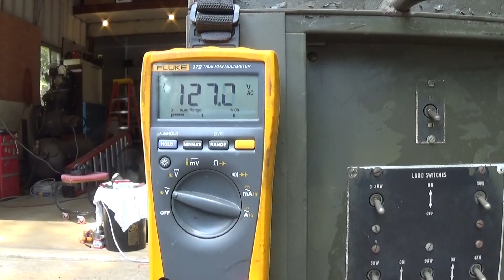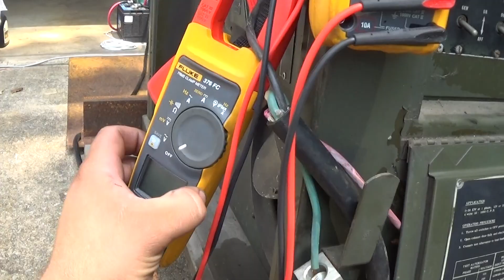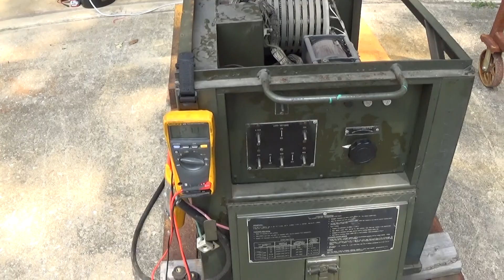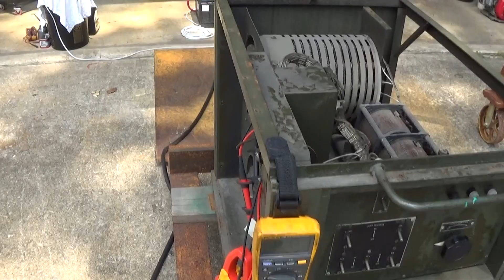I would expect nothing less than 60 hertz bang on from an inverter generator. This load bank has no real metering on it, so that's why I've got the two Flukes here for voltage and current. Now, in reading the manual for this little generator, it's possible to scroll through the menus on the little controller to see the generator's load in amps and kilowatts — that's about all you can see on that display. But it seemed a bit difficult to navigate, so we'll get back to that another day. We'll just make sure the thing can take some load here.